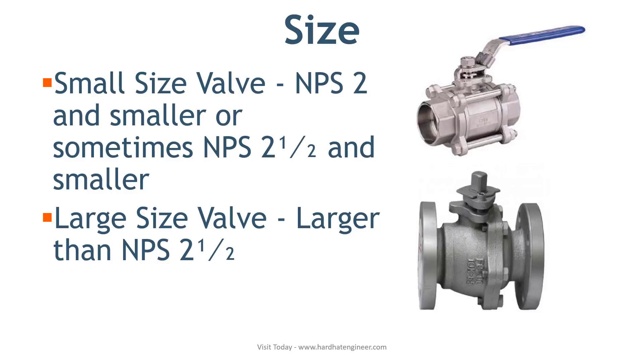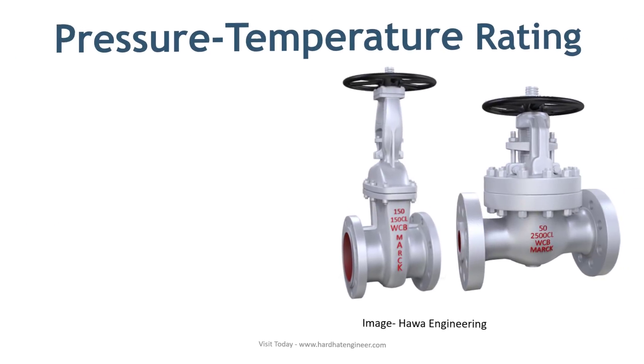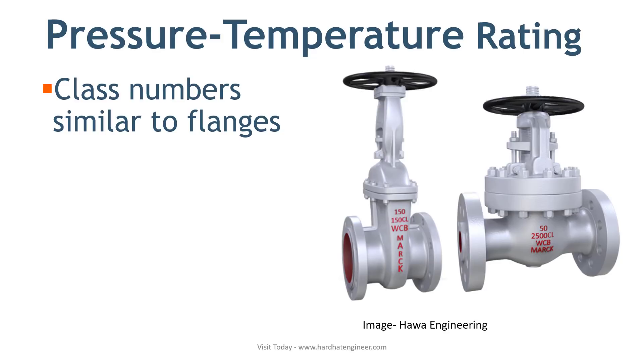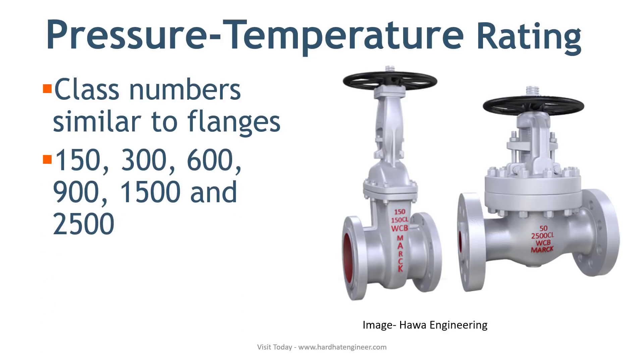Classification based on pressure-temperature rating. Pressure-temperature ratings of valves are designated by class number, similar to flanges. These class numbers are 150, 300, 600, 900, 1500, and 2500. Pressure-temperature ratings for each class of valve depend on the material of construction of the valve.